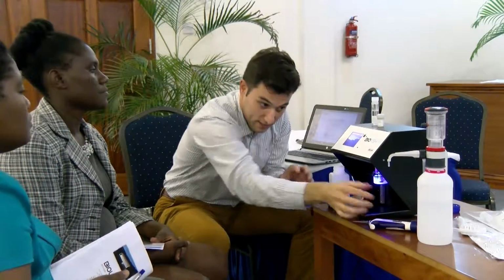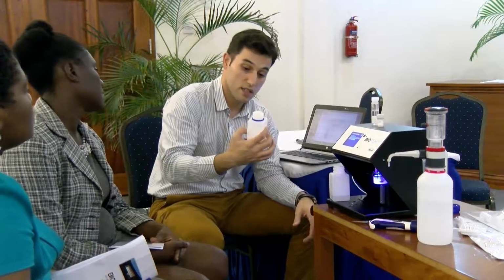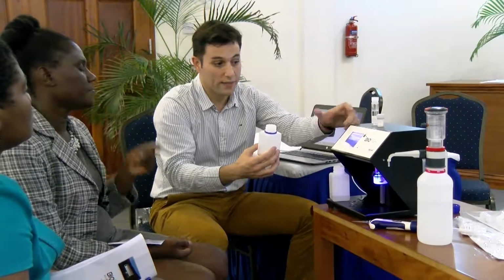As we made everything very fast, and normally it's recommended to let the samples rest a couple of minutes, we can find a possible difference. Normally we should have let it rest 2-3 minutes just to extract all the histamine. Normally the device has an error of 10%. If it gives you 20, it can be 22 or 18. This is the range normally.